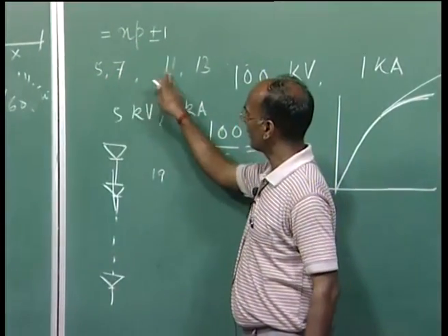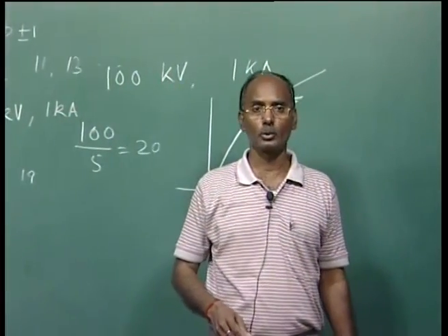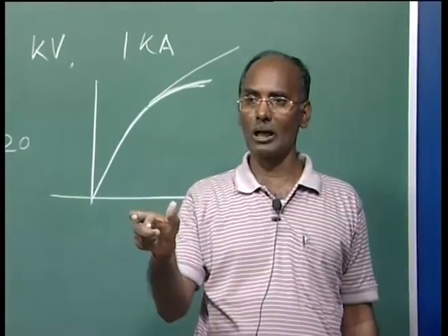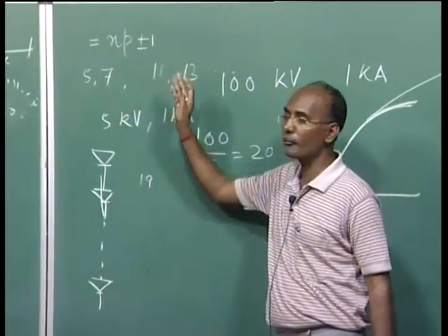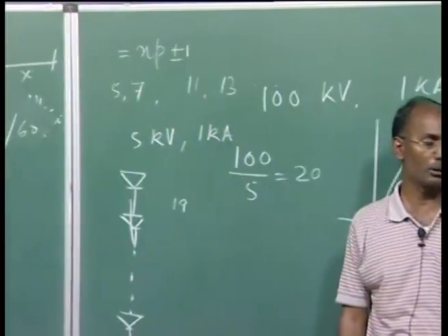Frequencies other than these may also be present in the system, and those are called non-characteristic harmonics, due to the overlapping of the valve conductions. We will see it is not only this, we also have some intermediate frequencies, and we should protect against them as well, but it is very difficult and their magnitude is very small. So we go for these because they have the lion's share, the highest magnitude, and we put filters for only a limited number of harmonics.